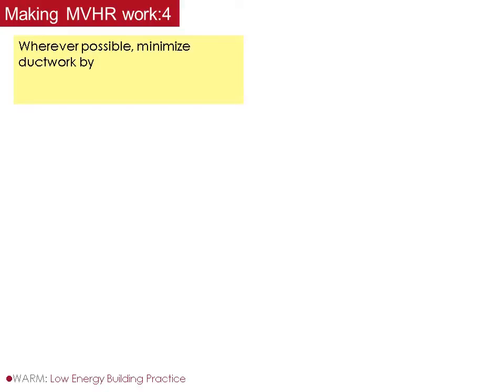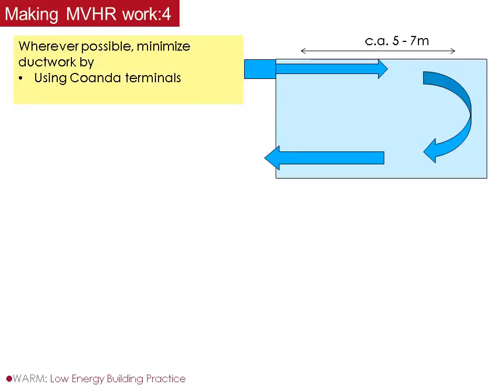Once you've got the general ideas about what you're going to do with the ductwork, you need to minimise it. Two little tricks that we use a lot in Passive House shorten the ductwork. The first is using coanda terminals. There's an effect called coanda where if you blow air into the room under a ceiling, it sticks to the ceiling and doesn't diffuse, as long as it's within about 8 inches, 200 mil. You can get 6 metres across the room easily. That means you haven't got to take the ductwork to the other side of the room, and your supply and extract are on the same side. That can make a substantial reduction.